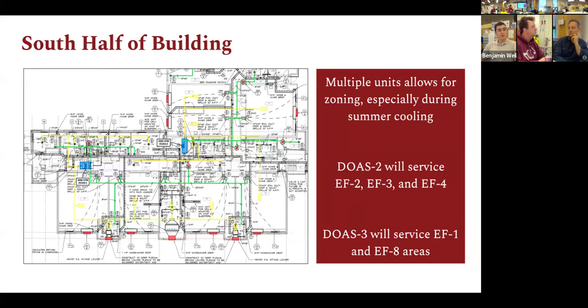So for the south side of the building, pretty similar situation. We have a few different zones, which is nice, so that if we were to say, in the summertime, have a summer program that maybe only runs in one of the classrooms, or there's people in the offices, you're able to zone the building so that you're not providing air conditioning for the entire space. The CFMs, so the 3,000 and the 2,000, those ventilation rates were calculated just based on the exhaust fans that currently serve those spaces. So they can be different sizes depending on the needs of those classrooms and offices.